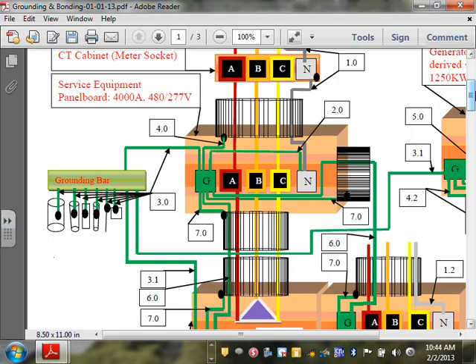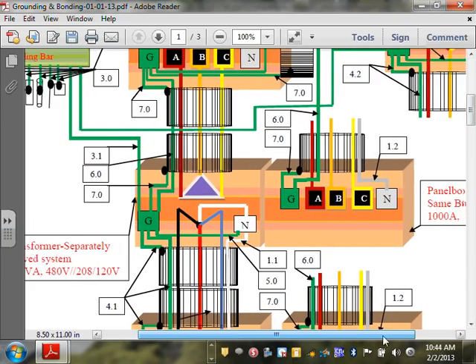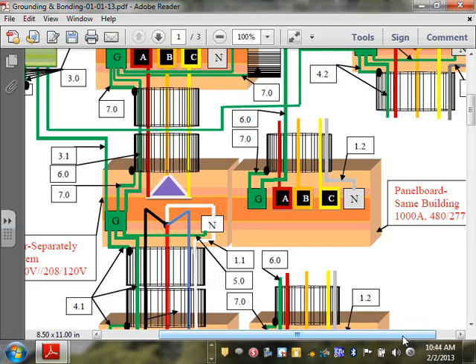I'm going to go to this branch because it's an easier branch. Suppose this branch happened to be 2000 amp, I think. I can't remember, here you go. So now I have a sub panel in the same building. I have a 1000 amp switchboard or panel board, typically panel board, at one end of the building, and I'm taking a feeder at 480. We have not created new voltage, 480, and I went to a sub panel in the second building. Now, a sub panel in the second building, be it in your house or in a building like this, be it 1000 amp or 100 amp sub panel, the grounding is identical, the same thing.